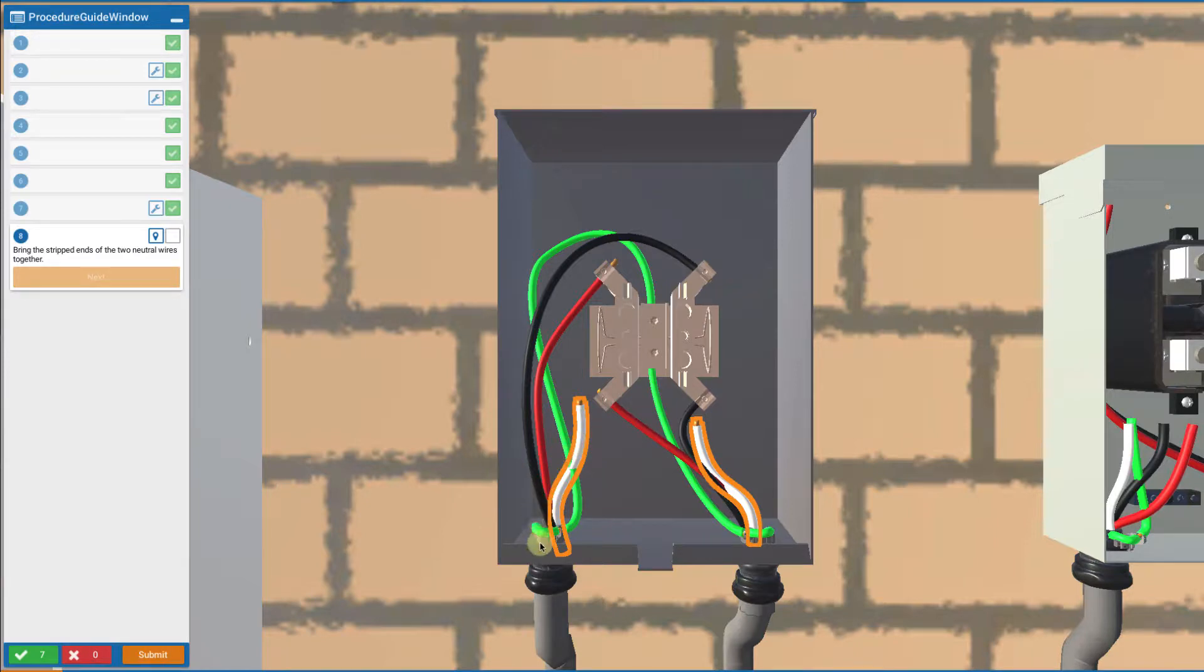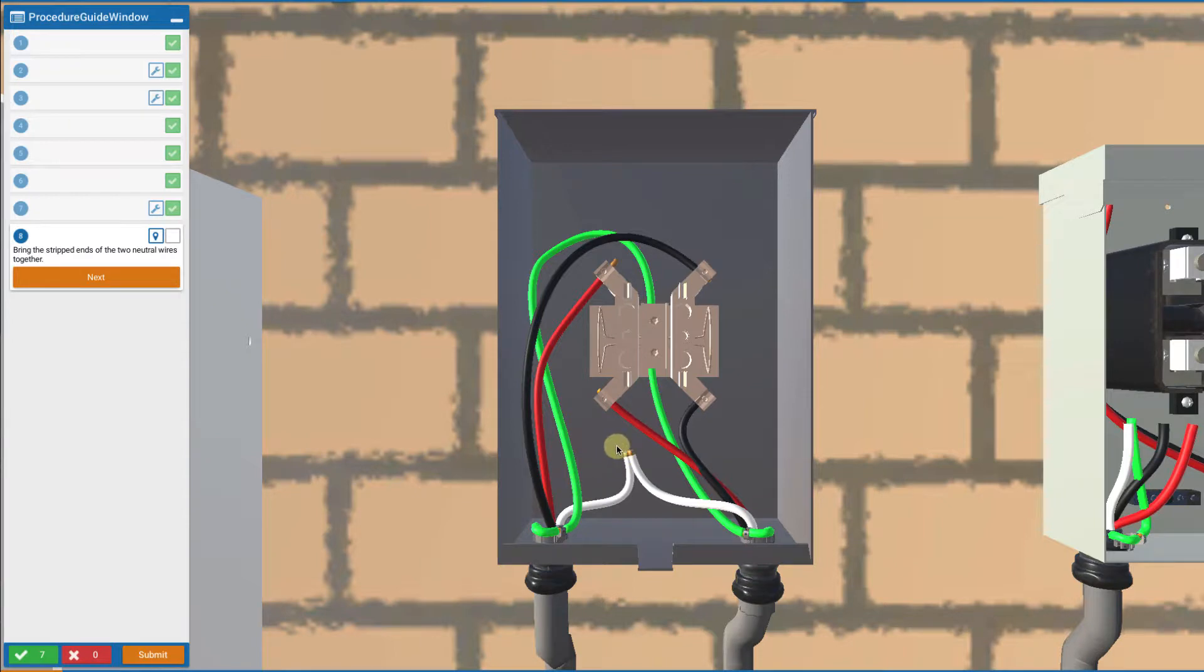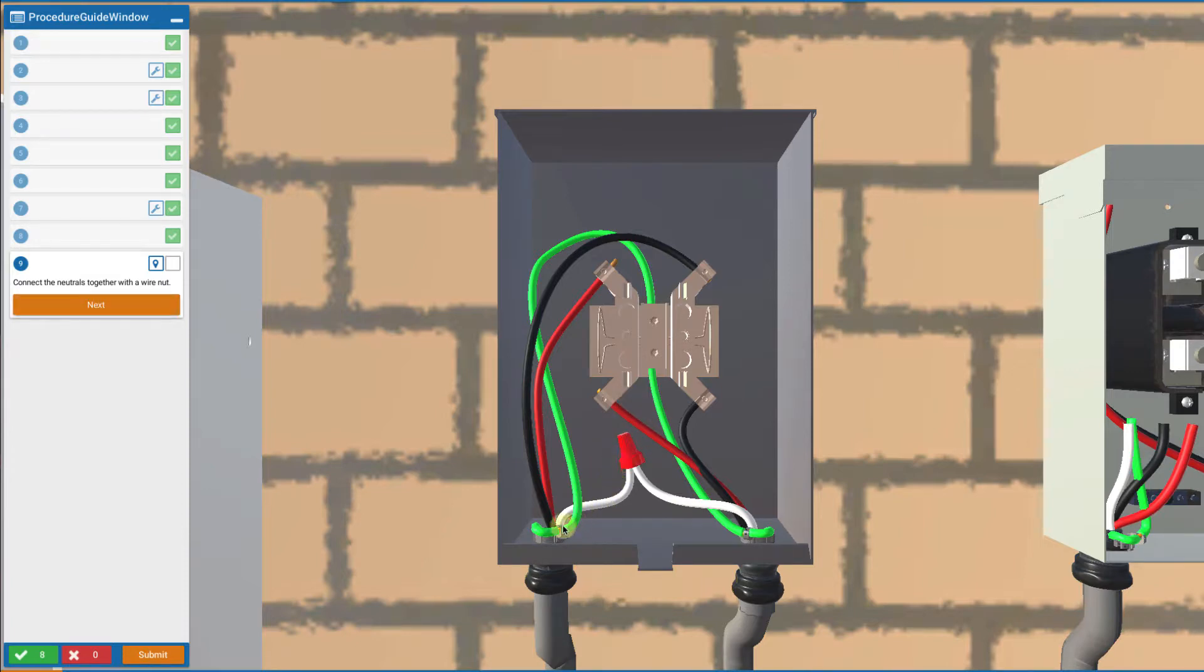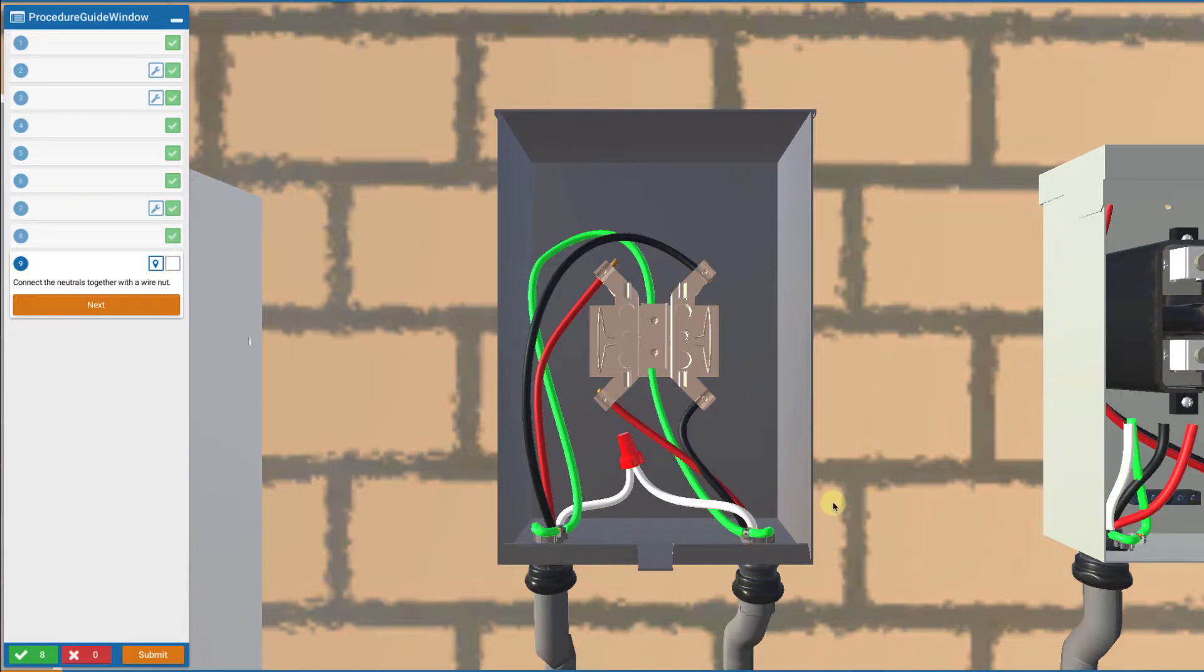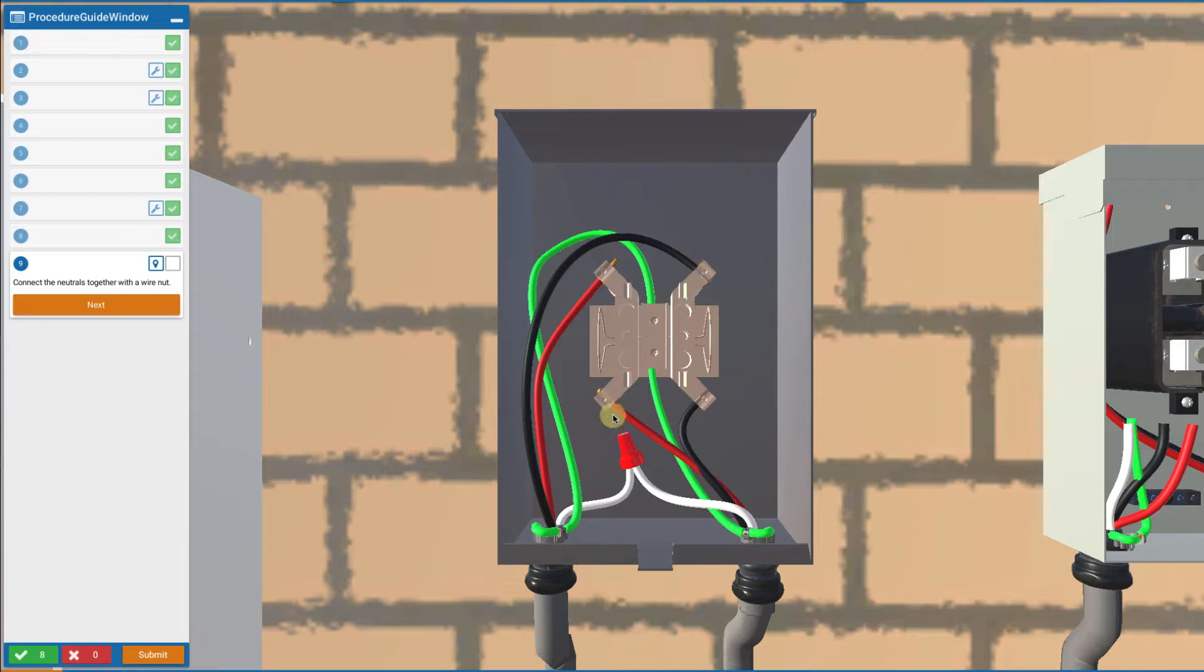Now what we did when we made this was we brought the neutral wire in from the inverter, stopped, and then we pulled a wire from the revenue grade meter into the AC disconnect. We're going to connect that neutral together. Touch on the two wires to bring them together and then add on a wiring nut by touching on it to connect those wires through. We could have pulled the neutral wire through unbroken and had it be a continuous wire all the way through. That's just fine. If it's easier to pull separate wires in and separate wires out and have them all separated, that's another technique and that's what we've done here.